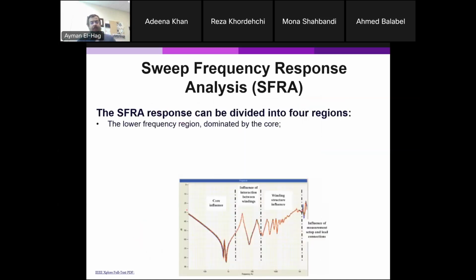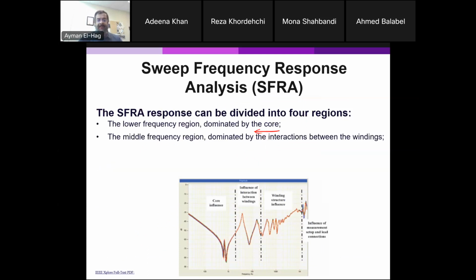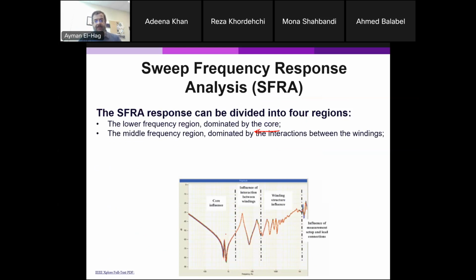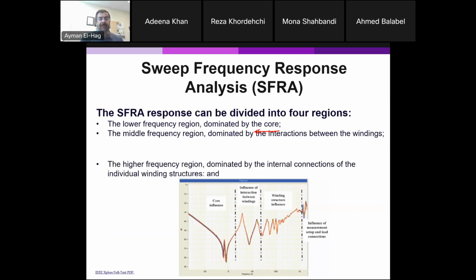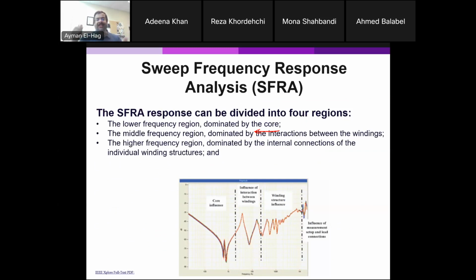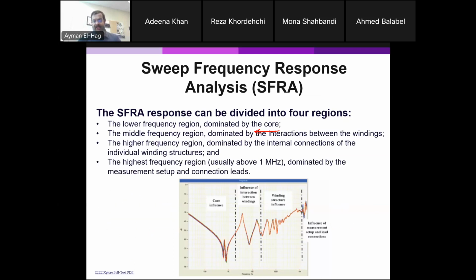It can be divided into 4 regions. The lowest frequency region is dominated by the core, meaning that if there is a defect in the core, you will see some discrepancy in that region. In the middle frequency region, there is a problem between the windings. So that reflects the interaction between the low voltage and the high voltage windings, the low voltage and the tertiary winding, and so on and so forth. Then a bit higher, this is the winding structure within themselves. So if there is an issue within the high voltage winding or the low voltage winding, it can be reflected in that region. Finally, the highest region is basically from the setup and the lead connections.